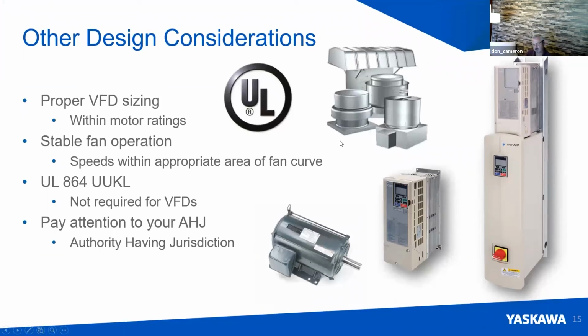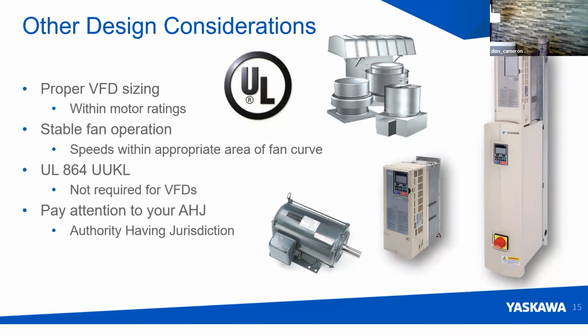And this is actually our last slide. It's very critical to correctly size drives. Drives that are undersized won't work well in these situations. You never want to have a 230 volt or a 460 volt situation where you're selecting the wrong drive, obviously. But more importantly, the fan curve is critical to make sure that it works. And again, I can't reiterate enough, UL 864 has nothing to do with drives. I'm grateful for that because it makes life easier, but it makes sense that people would think that. If someone asks you that, that's not really a thing. And again, Denver in particular is a very unique market where you could show up to a job site and find out that something's not working right. The good news is, again, the drive can be programmed to do whatever it is you're trying to do. That's it.